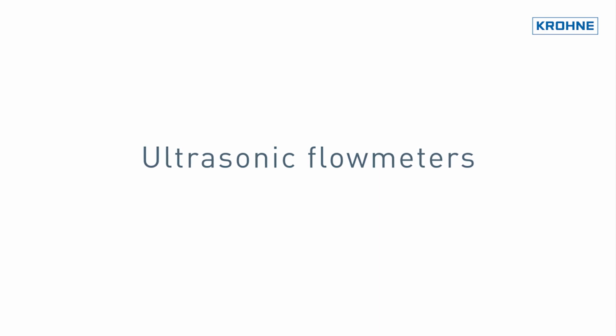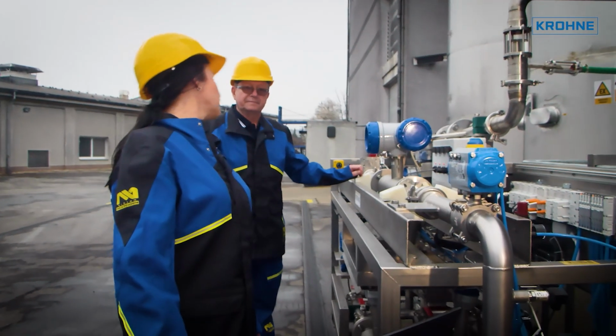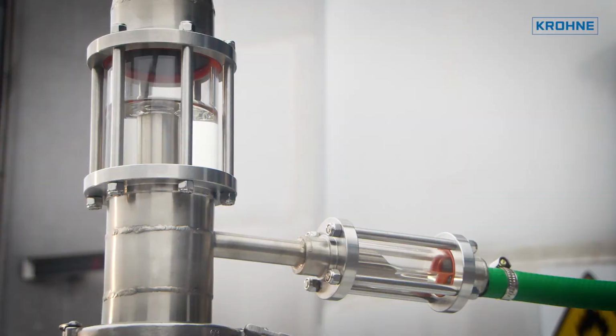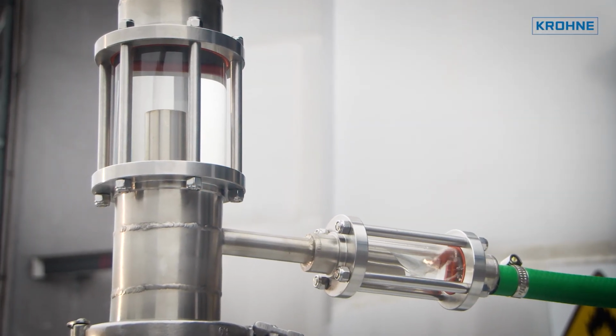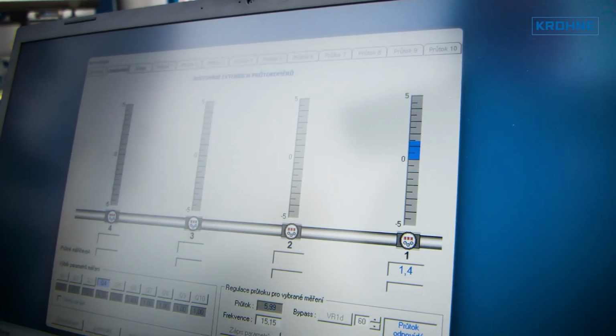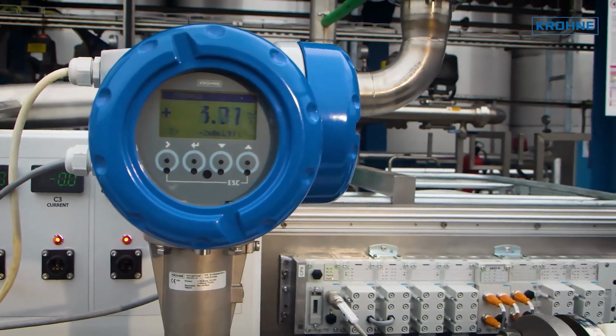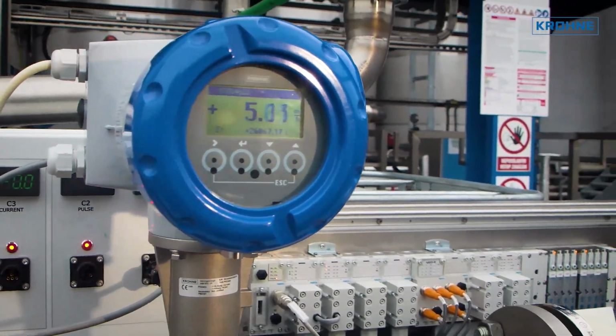Ultrasonic flow meters, both stationary inline and portable or stationary clamp-on, can be calibrated. Verification on the rig is done with water, via the volumetric method with flying and fixed starts.